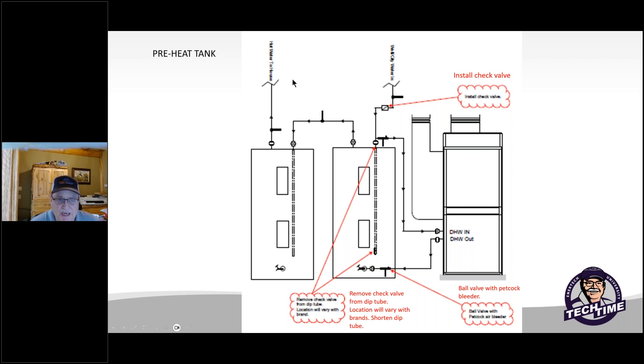Basically the mixing valve will take some of the cold water, temper it with the hot water, and that also increases the capacity of the water tanks. Some things to consider: think about a check valve depending on the vessels that you use. Is there one there? Is there one stopping the water flow making it hard to make this loop?